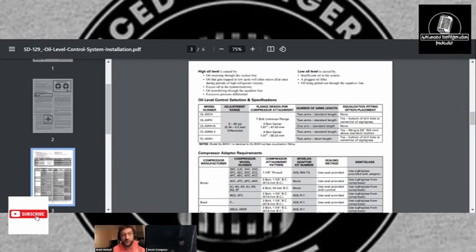Not every single compressor, but some manufacturers fill up to a certain level above the manufacturer spec, and they don't like it. The crank ends up slapping in the oil and tossing it all the way around, and it makes its way to the piston and crunches all the valves. Or the crank goes snappy. Once again, Voldemort - that should be the new code word. Everything's Voldemort from now on.